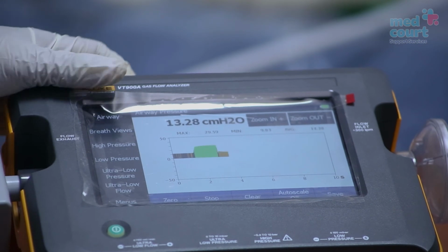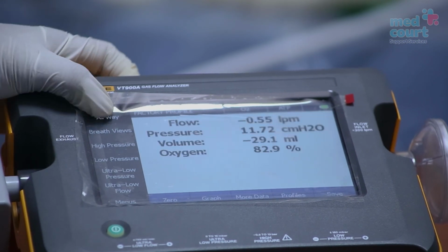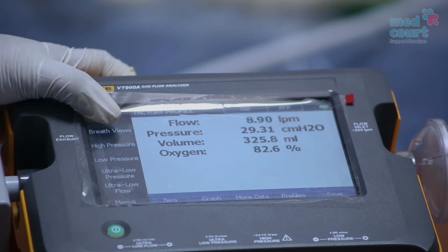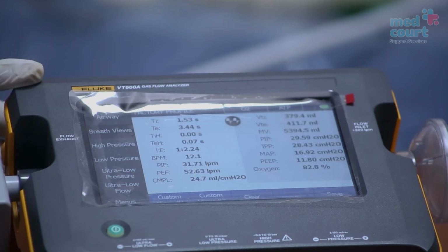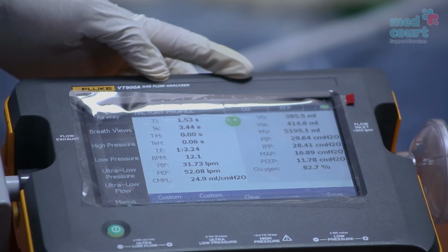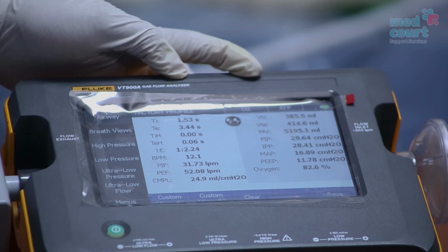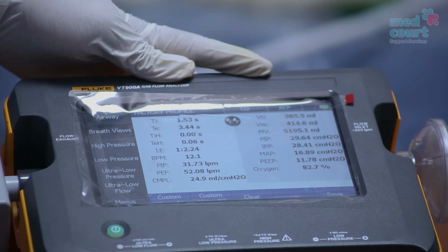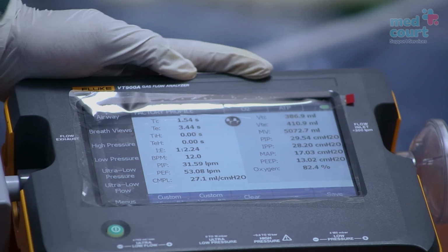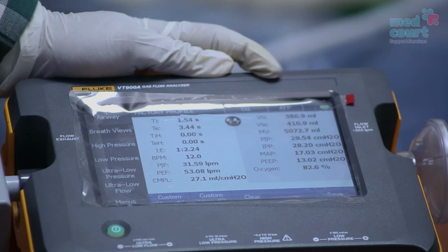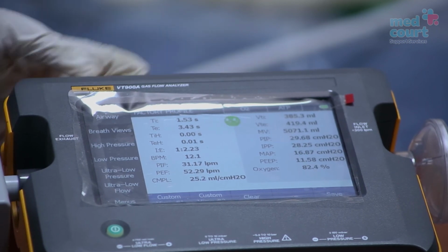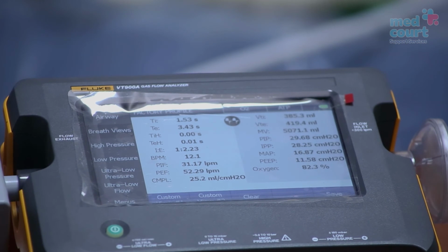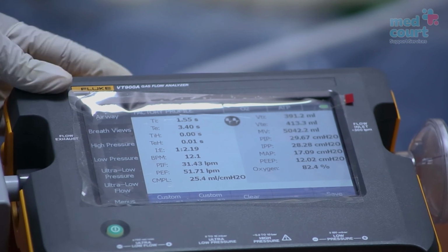Go back to the airway option. In the breath views mode, you can also compare the different parameters as mentioned earlier to that of the ventilator. For instance, the oxygen percentage here is 82.6, while on the ventilator we have set an oxygen concentration of 80%. Click Save.